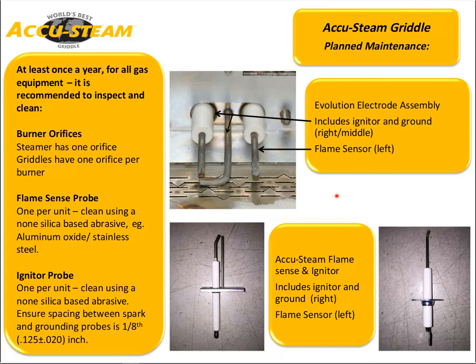The last thing I'll touch upon is our ignition probe. There should be a gap of around 1/8 of an inch, or 0.125, between the grounding probe and the igniter. If that spacing gets wider, it can cause the igniter spark to come further back. That can cause delayed ignition, backfires, which will eventually damage burners as well. So that gap is really important, and I highly advise you inspect that if you're having any kind of ignition issue with a piece of AccuTemp equipment.